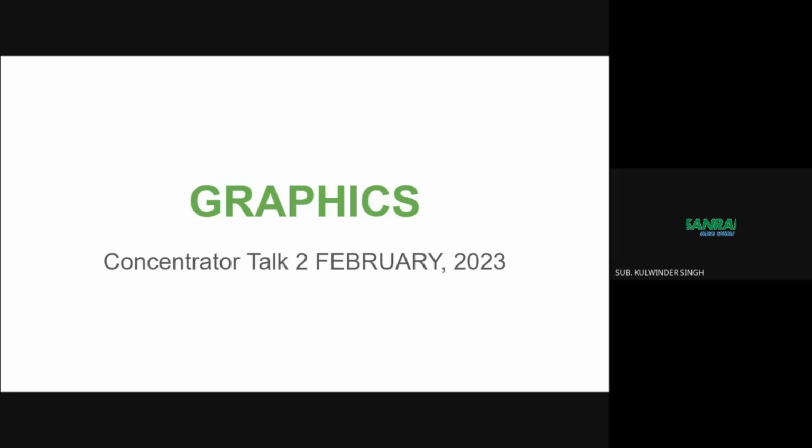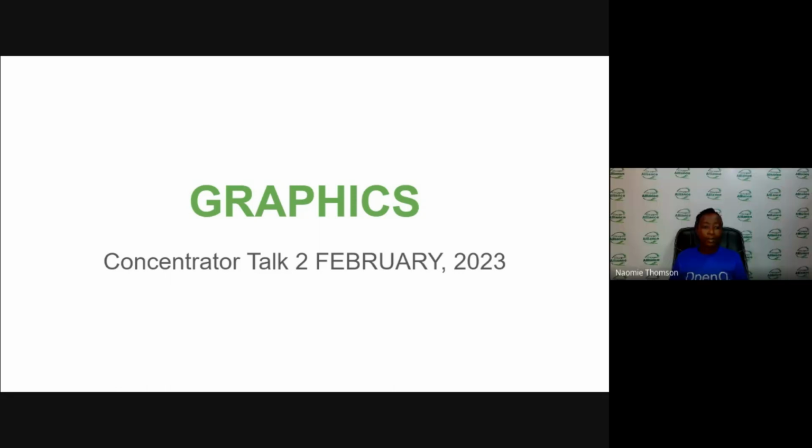I am sure the performance of your machine is going to change. You need to be extra careful when replacing control boards of any oxygen concentrator, making sure the replacement is of the exact model as the one you are working on. Thank you. Thank you very much, Kowinda.